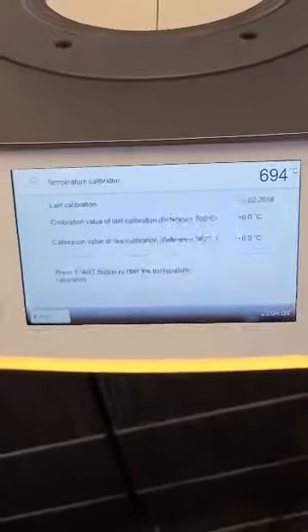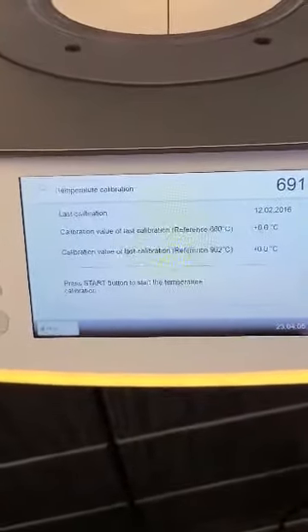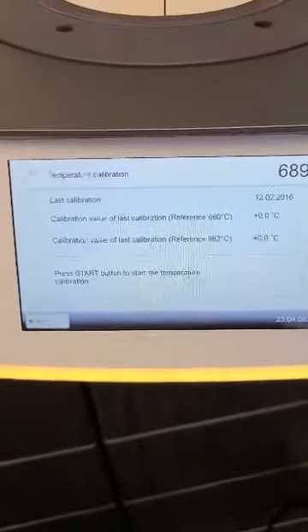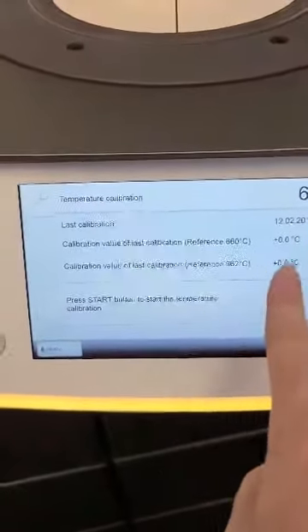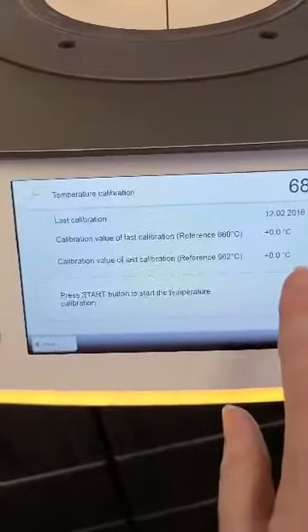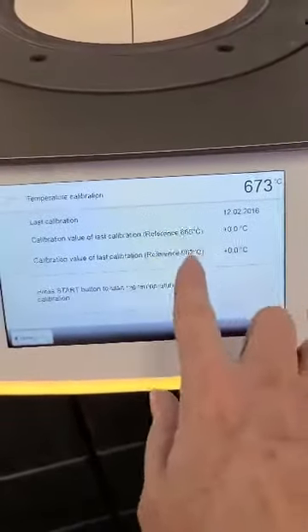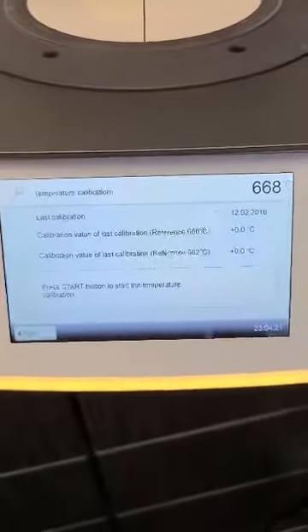It shows you the date you last calibrated. Again, this should be something that you do every year. And it tells you also if it was successful or not successful. And it gives you the readings. So those are the numbers that you're looking for. If you have your oven set to Fahrenheit, you'll see those numbers represented in Fahrenheit.